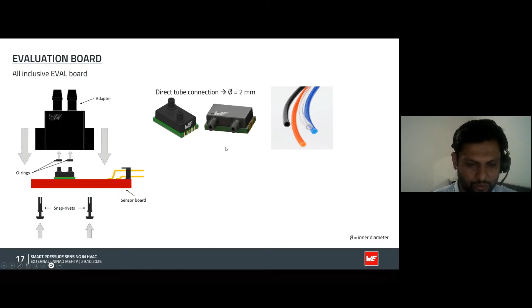An important aspect is which kind of adapter you might want to employ in your system. For manifold mounting, we always recommend that adapter be placed on top, because it gives better mechanical stability. When tubes are directly connected to the sensors, there is a very high amount of stress transferred to the solder joints, and solder joints are made to withstand electrical stress rather than mechanical stress. So this gives you additional safety against leakage or dust which might get inside.